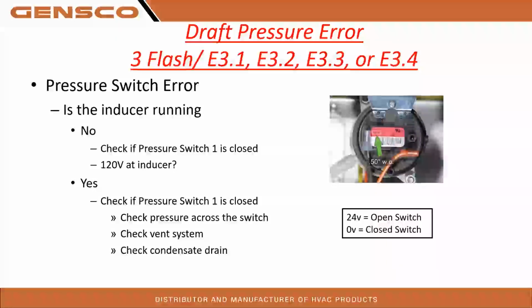All right, so draft pressure errors we're going to look at. Obviously, pressure switch error, is the inducer motor running? No. Okay, well, that's a problem, right? So we need to see if pressure switch 1 is closed. Is there voltage at the inducer, 120 volts, or even if it's a variable speed inducer? We're going to look if the board's sending any kind of voltage. Okay.